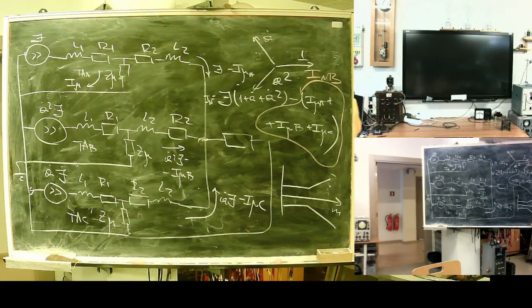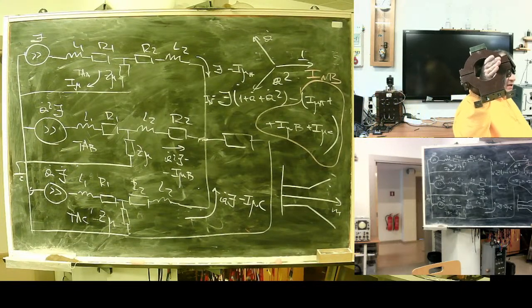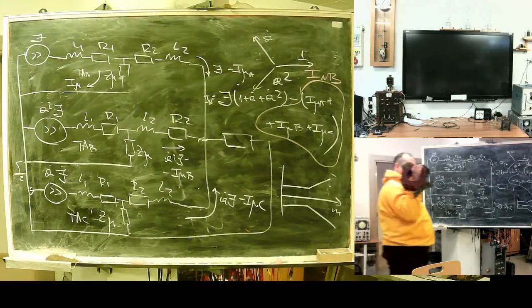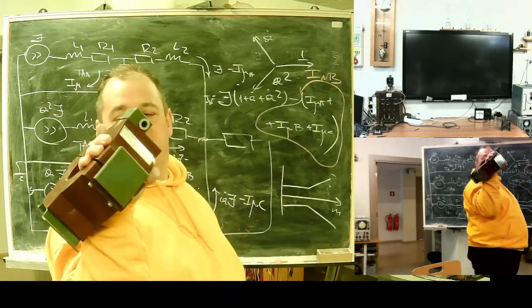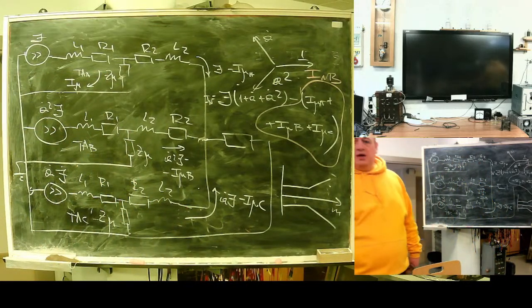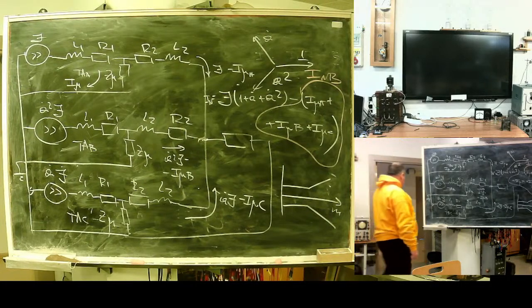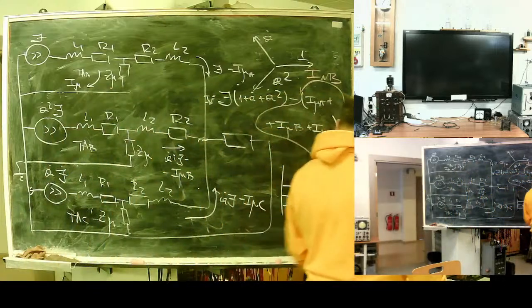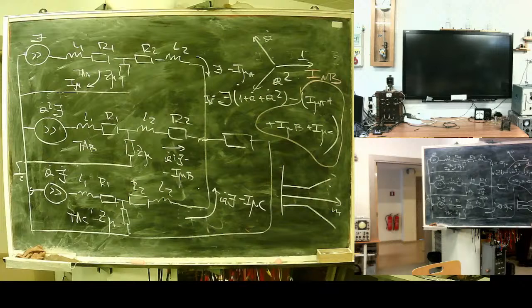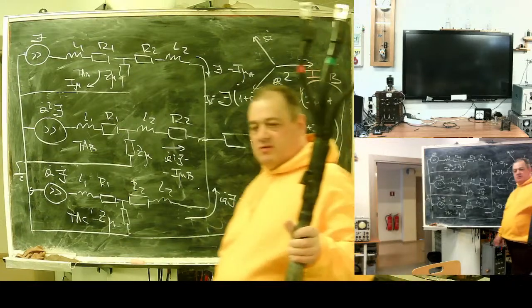How to get it? Come here. Solution is here. Solution to your problem. In local terms, it's a Ferranti transformer. A special transformer in two parts. It's a so-called cable transformer. Take your high voltage cable. Take your cable.